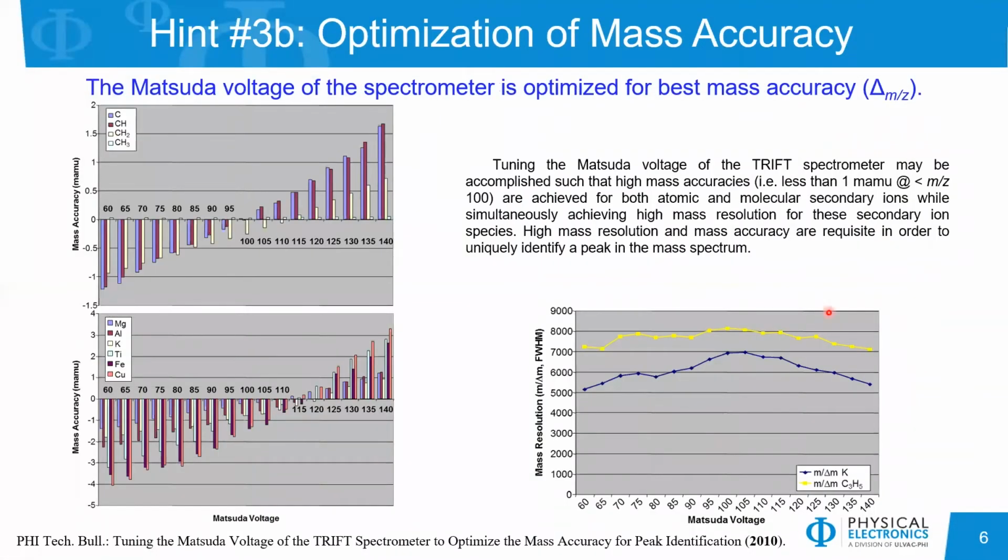And that peak centroid position can have a big impact on your mass scale calibration. So some of you might notice that if you calibrate your mass spectrum using organic ions, then the peak assignments for your atomic ions or your inorganic ions become a little more unstable or a little more difficult.